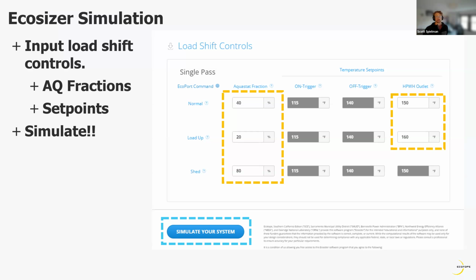The way that we've been successful doing heat pump water heaters in the field is a little bit different than just set point control. It's a little bit more complicated. The storage volume is larger. So we use what we call aquastat staging. And basically all that means is that we have multiple temperature sensors within the thermal storage tank. And then we change which ones we are referencing to turn on and off the heat pump, based on what operating mode we are in.